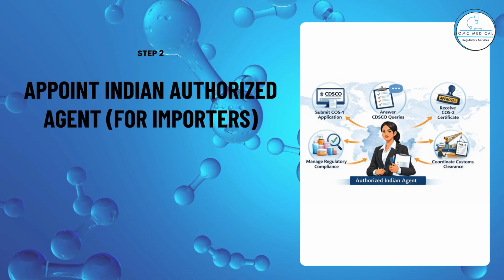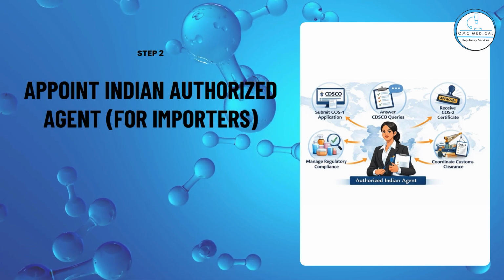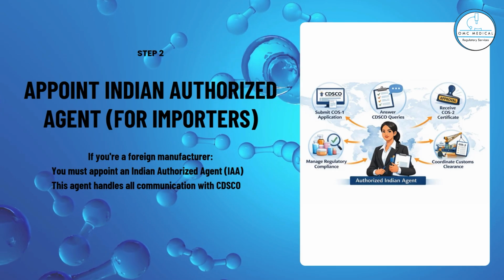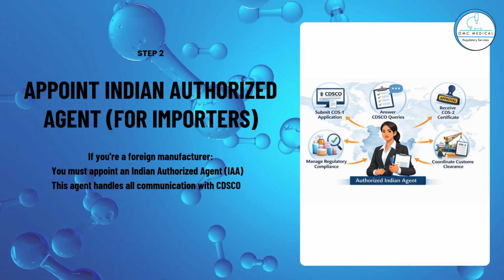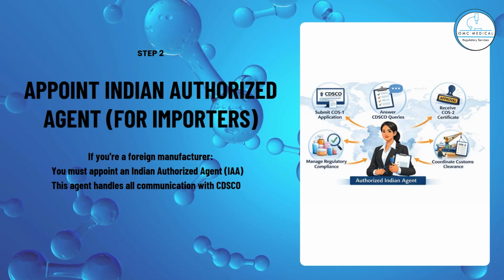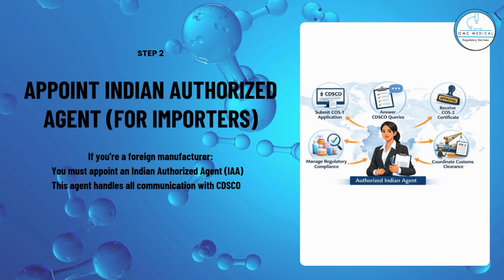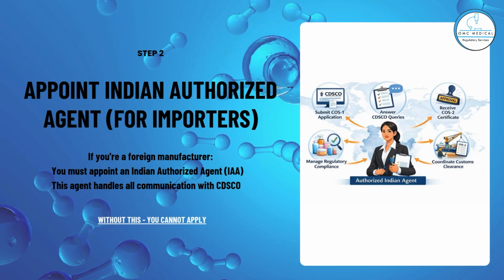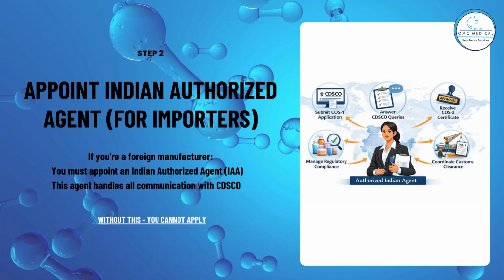Step 2. Appoint Indian Authorized Agent for importers. If you're a foreign manufacturer, you must appoint an Indian Authorized Agent, IAA. This agent handles all communication with CDSCO. Without this, you cannot apply.